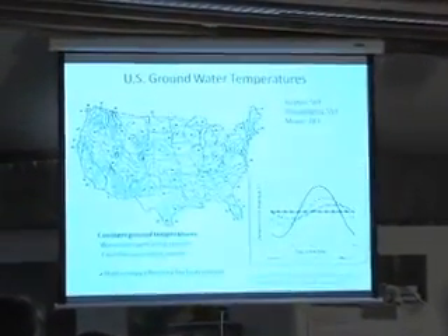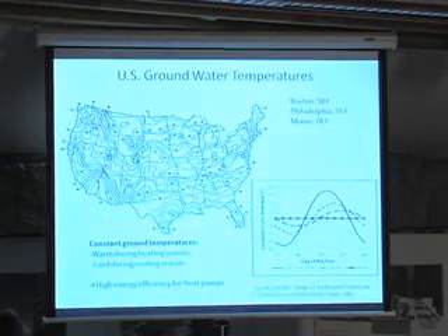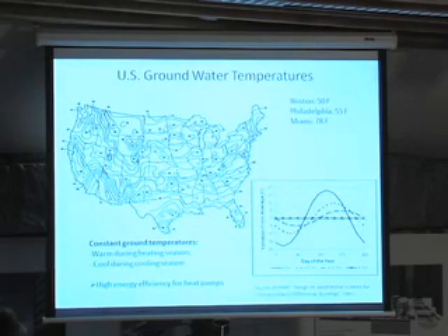Excuse me, at what depth is that? Well, good question. Now look at this chart here. This chart shows the temperature variation around the average temperature in the ground across the year. Now, this line shows 2 feet below ground. Okay, it changes a lot through the year. 5 feet below the ground, dotted line, changes somewhat. 10 feet changes a little bit. When you get down to 30 feet, it doesn't change. So basically that ground temperature means below 20 feet, 25 feet.